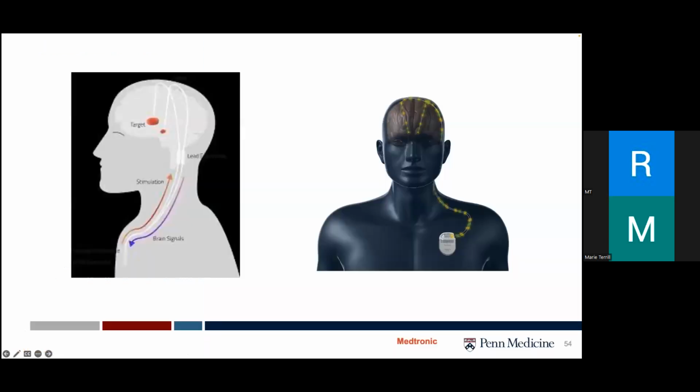A quick word on DBS as a closed loop. It's also an emerging approach in the field of neuromodulation. DBS devices have the capability to sense neural signals like local field potentials and use this information to adjust the delivery of stimulation in a closed loop manner. The Percept device with BrainSense technology allows for capturing these local field potentials, which can be recorded simultaneously while you're delivering therapeutic stimulation. This enables more personalized programming, and you can tailor it to patient-specific needs.